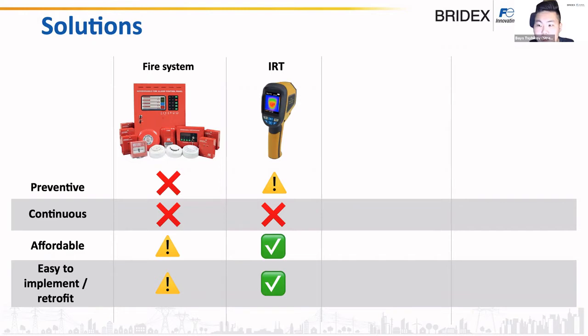Infrared thermography, which is used in most factories and utilities now, can be not so preventive because it has limited visibility and limited accessibility. You cannot check every single spot inside the electrical panel because you just cannot see them through this camera. If you have a long period between two inspections, let's say 2 years or a year, the problem can occur and lead to a fire between these two inspections. In that case, we cannot say that infrared thermography is a preventive solution. And it's not continuous as well, because it's periodic, time to time. Yeah, it's not continuous at all. But it's kind of affordable, and it's really easy to implement. You just need to buy a camera and teach someone to use it.